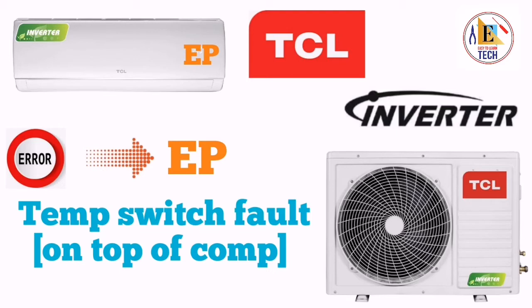If the temperature is not high, then you have to short circuit CN3 on your power PCB board, and if the problem is solved, it means the temperature switch is faulty. You need to replace the temperature switch. And after replacing, again if it is not working, then you have to change your outdoor PCB board and your unit will be in working condition.